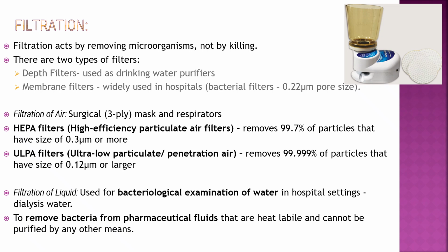Filtration of air: surgical three-ply mask and respirators. HEPA filters, high efficiency particulate air filter, removes 99.7% of particles that have size of 0.3 micrometer or more. ULPA filters, ultra low particulate penetration air, removes 99.999% of particles that have size of 0.12 micrometer or larger.